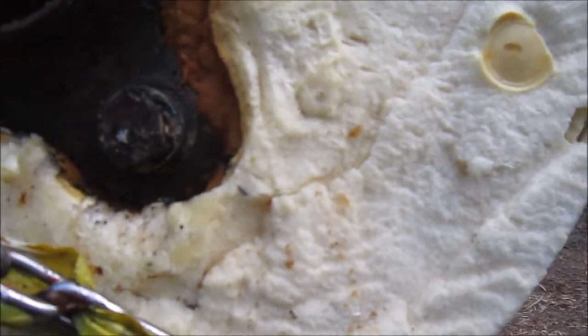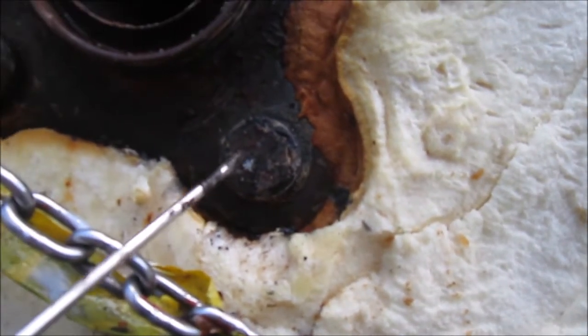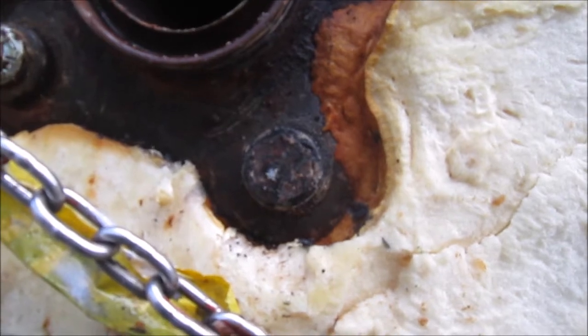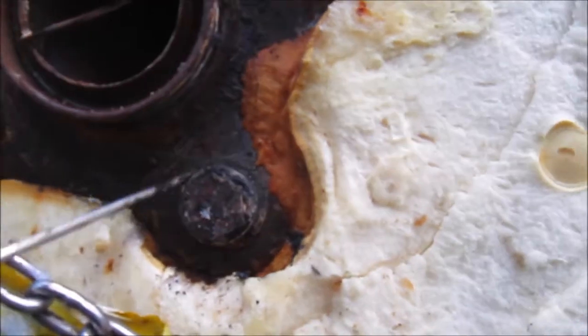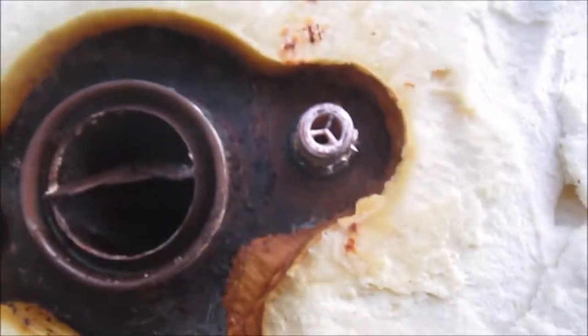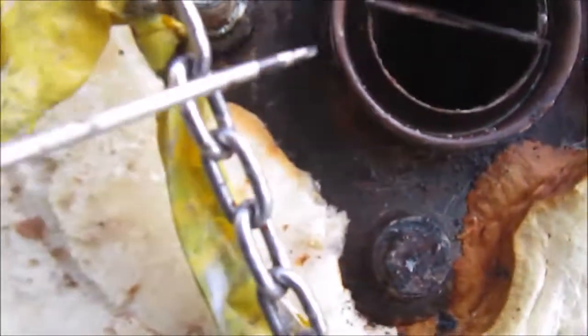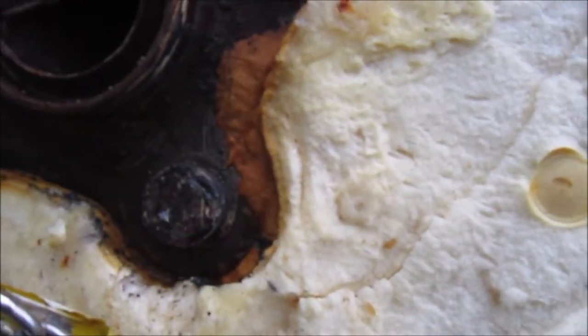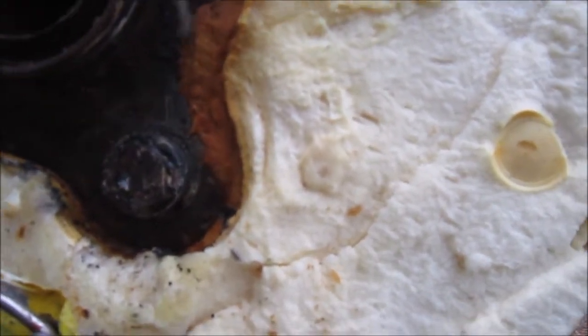That thing is shot. I can tell just by the way that sounds, it's like the corrosion resistant bar or whatever, the zinc bar that gets in there and prevents the other pipes from corroding. This corrodes first. That thing doesn't sound like it's in there. So nothing I can point out exactly, but it definitely looks suspect up in here. This rust here is pretty bad. Yeah, right where that thing connects, probably is where it went bad.